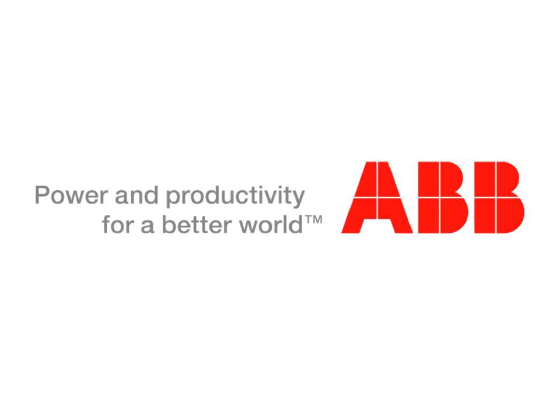Yes, that's right. So that methodology for solar gain is actually given in API 521. So that's the best guide for those thermal expansion cases, and it will tell you the key thing is to work out what your worst case heat input would be, and that, for thermal expansion for solar gain, will depend on whereabouts in the world you are.